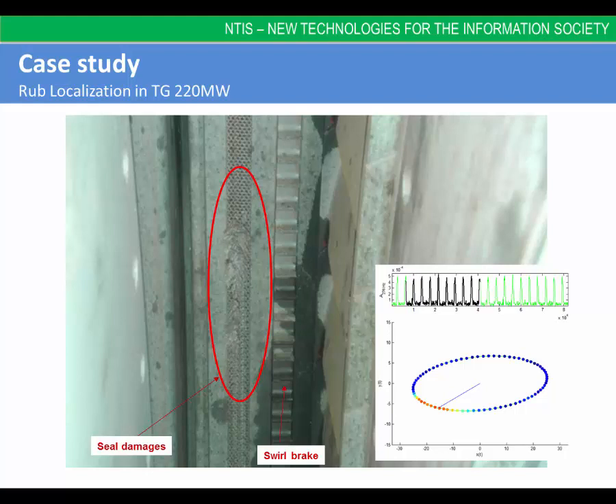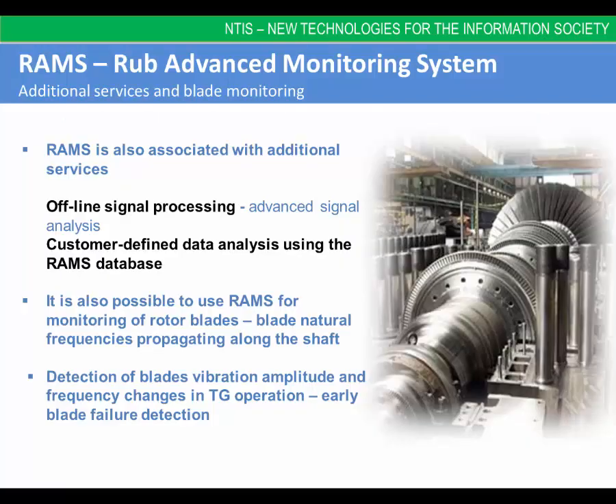The identified circumferential angles were also confirmed by the turbine inspection in the summer of 2012. The RAMS system is also associated with additional services related to vibration diagnostics based on advanced signal processing and analysis. The RAMS also allows performing customer-defined data analysis. The recently developed module for RAMS enables monitoring of rotor blades — blade natural frequencies propagating along the shaft are monitored through the existing shaft proximity sensors. The new module detects blade vibration amplitude and frequency changes in turbo-generator operation, with the aim of detecting the initial phase of rotor blade failure.